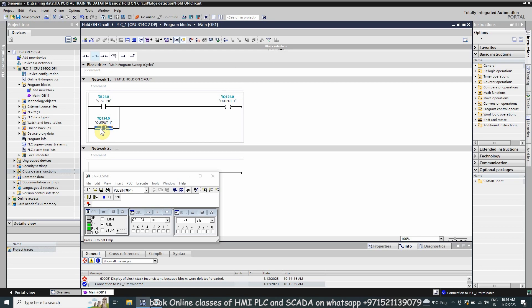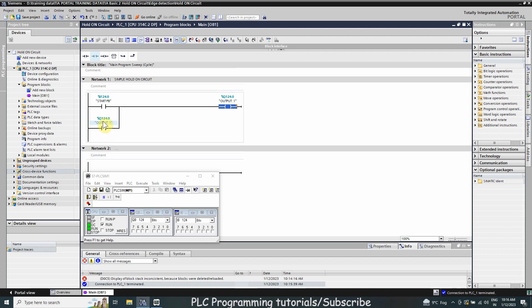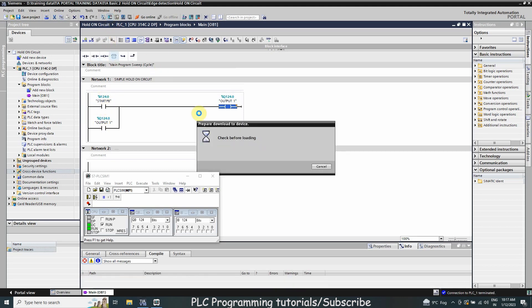We assign this normal open contact the address of output coil Q124.0. Whenever the output is energized, this NO contact will also close. The logic is: as soon as we press the start push button it energizes Q124.0, and at the same time the normal open contact of Q124.0 also closes — so through this contact the output remains on even if we release the start push button I124.0. We then load this program into the PLC.